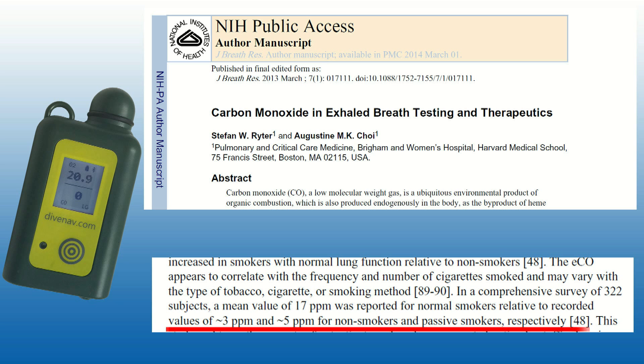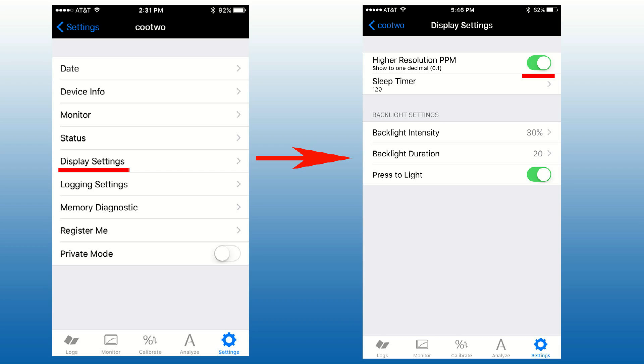According to a paper from Ryter and Choi, the exhaled CO value of non-smokers could be about 3 ppm, while the mean value of exhaled CO for smokers was 17 ppm. Before you perform a breath check, you might want to enable the display of the decimal digit.